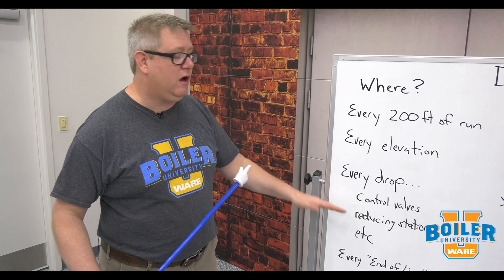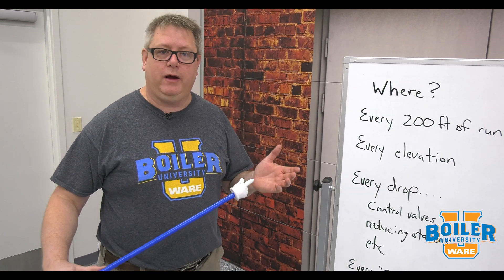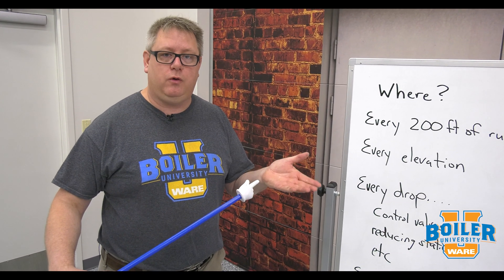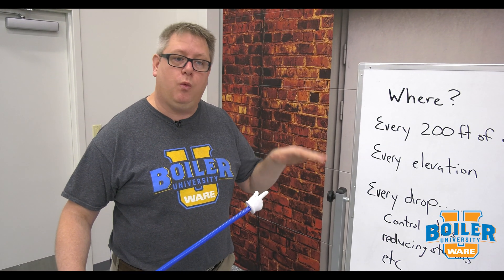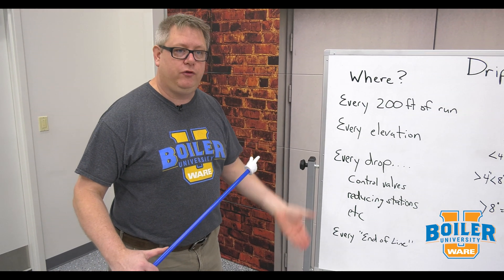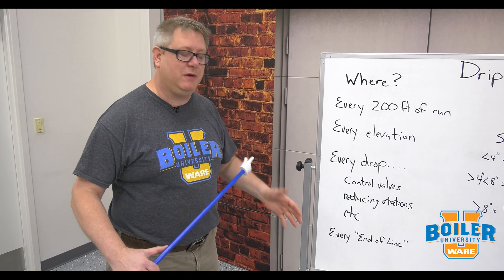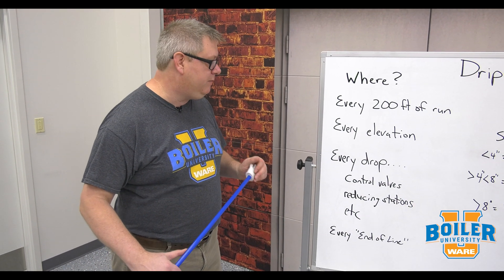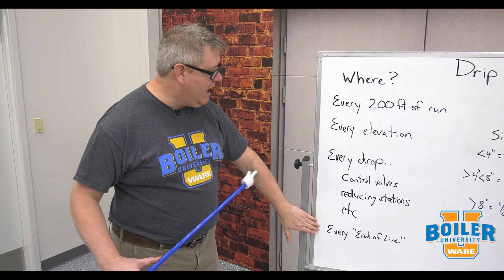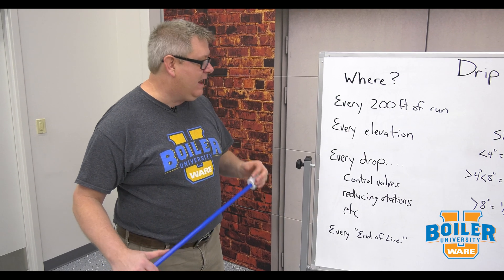Presumably if we've got a control valve, at some point it's going to be closed, and so when it's closed that upstream piping will flood with condensate. So the drip leg and trap keep that clear.